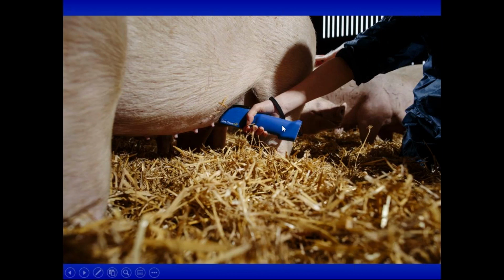This is another kind of transducer that works in the same way. The crystals are here. This is a sectorial, sorry, it's a convex transducer. And the electrical pulses are generated here. They make the crystals vibrate. This vibration travels through the body of the animal, and the echoes come back and make these crystals vibrate, which generate electrical pulses that will be transmitted to a monitor that can be your cellular or tablet, and this monitor will interpret the image generated here as electrical pulses.